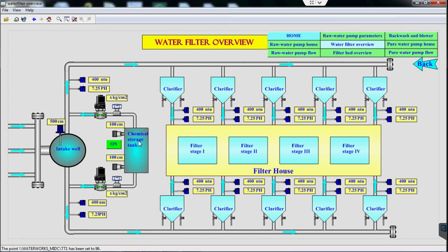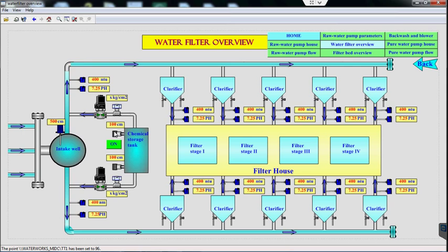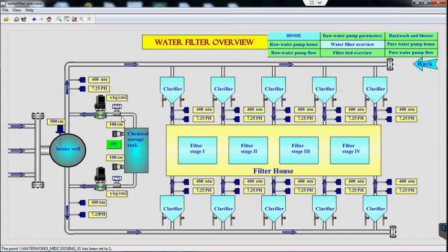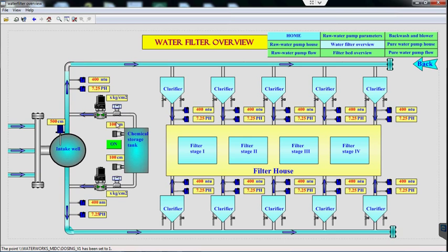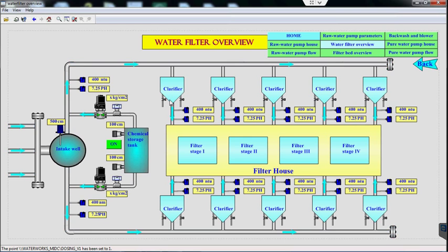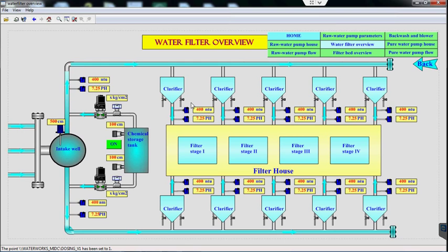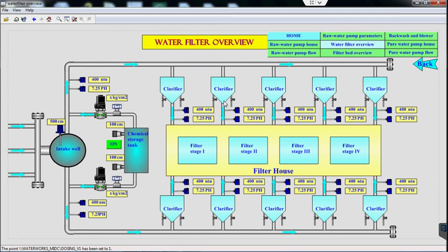A chemical dosing tank is located near the well and is provided with a level transmitter. Chemical can be dosed into raw water in two different streams. A control valve is provided on each chemical dosing line to control the dose, and a flow transmitter is provided on each chemical dosing line to measure the dose. Based on the turbidity and pH measured in each raw water stream, the chemical dose can be controlled by the dosing control valve. The chemical dosing system is provided with a micro PLC and HMI, wirelessly interfaced with the Stage 1 master PLC. Water is clarified in each clarifier, where algae and other solids settle down. Clear water is then passed to the filter bed. Each clarifier is provided with a micro PLC and HMI, which is wirelessly interfaced with the various stages of master PLCs.